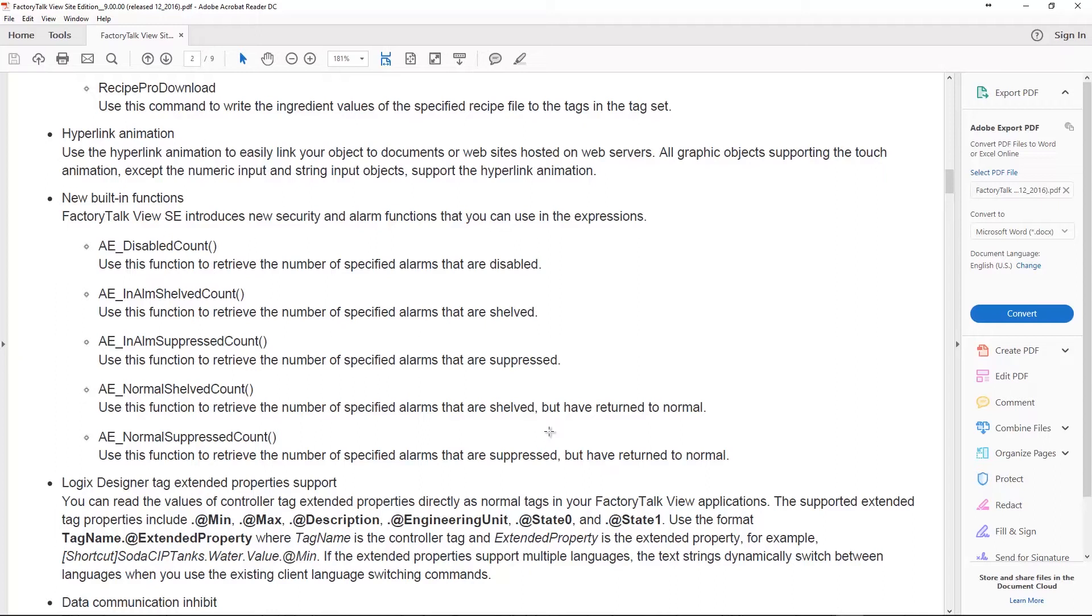In addition to that there's some new built-in functions for FactoryTalk Alarm and Events. Basically these functions give you the current count. That was one of the cool things about the old system tags, it told you how many alarms were suppressed and how many were active. Well they added a bunch more functions just for Alarm and Events including the number of disabled alarms, the number of alarms in alarm but shelved, and the number of in alarm alarms and suppressed, the number of normal alarms shelved and the number of normal alarms suppressed. That was a mouthful but hey, options are great right? And having all these new functions just makes designing graphics that can take advantage of Alarm and Events that much easier.